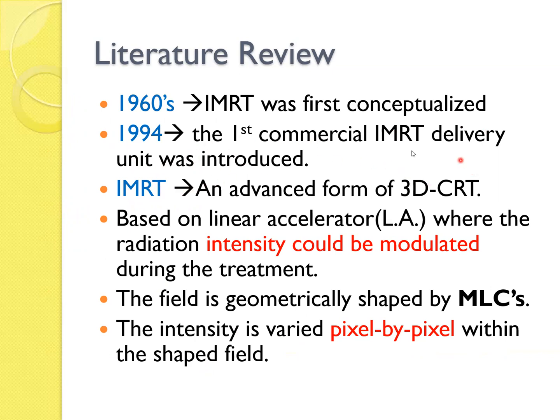IMRT is an advanced form of 3D CRT based on linear accelerator. Today we do have some modalities like tomotherapy, Halcyon, all those technologies used IMRT or advanced IMRT like VMAT. Where the radiation intensity could be modulated during treatment, the field is geometrically shaped by MLCs. The intensity is varied pixel by pixel within a shaped field.